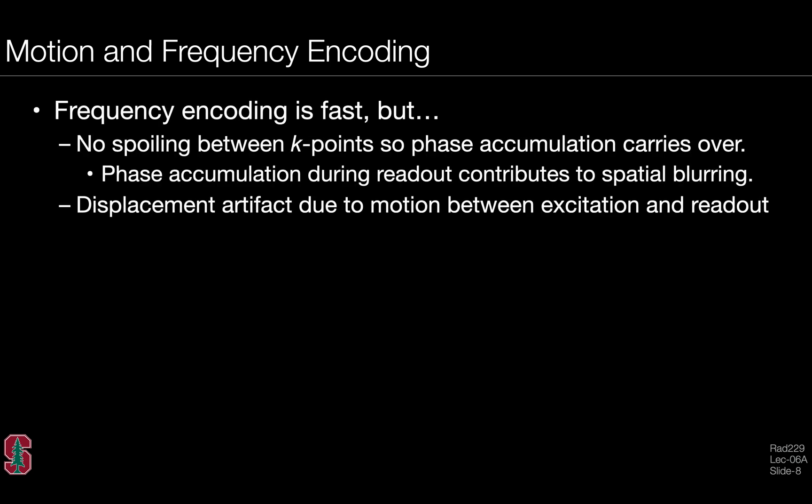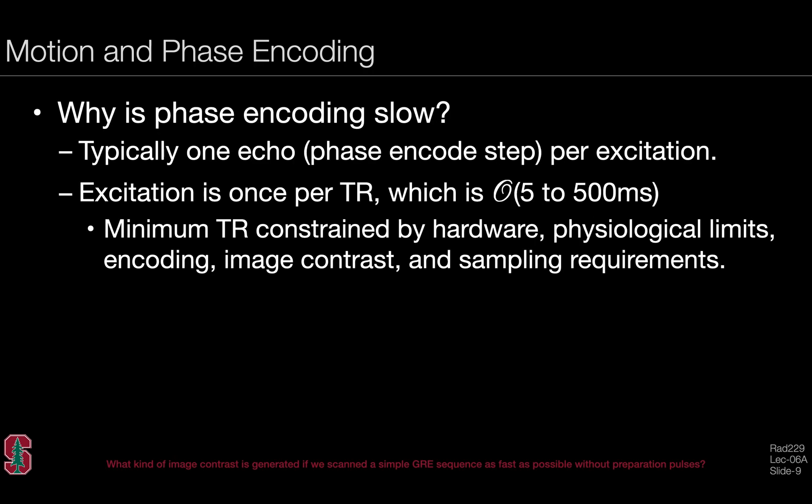Frequency encoding is fast, but there's also no spoiling between the K-points. Phase accumulation carries over. Any phase accumulation during readout will actually contribute to spatial blurring. Mathematically, we can see this as a broadening of the point spread function. You also can incur a displacement artifact due to motion between excitation, which happens at the beginning of the TR, and the time of readout, or the echo time, which occurs later in the TR. The time difference between excitation and readout compounds with the underlying velocity to lead to a displacement artifact of spins.